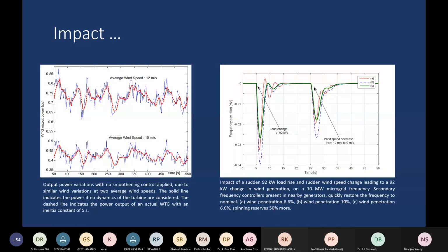So which means that if the wind is blowing at very high speed, and at that very high speed the wind fluctuates, then the impact on the grid is much more compared to if the ambient wind speed is low, but the fluctuations are the same. This is a matter of concern.